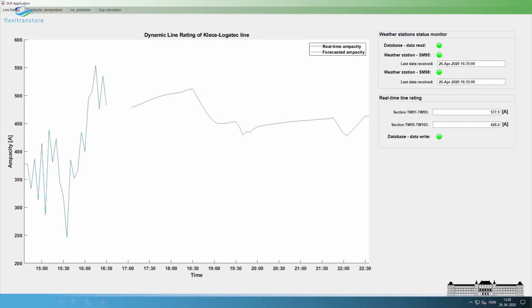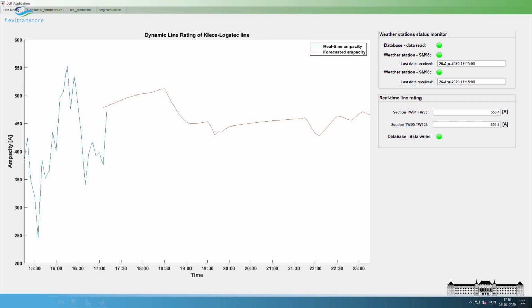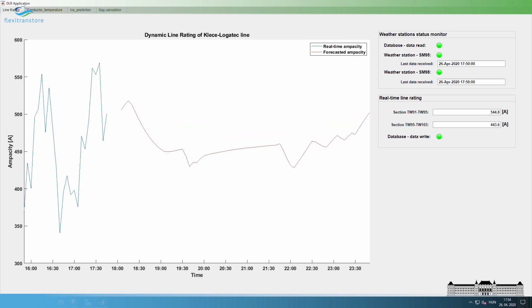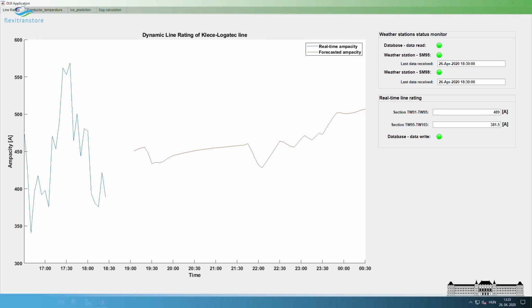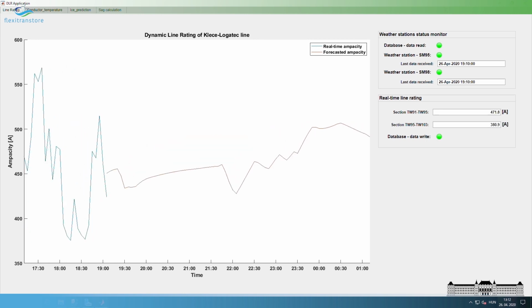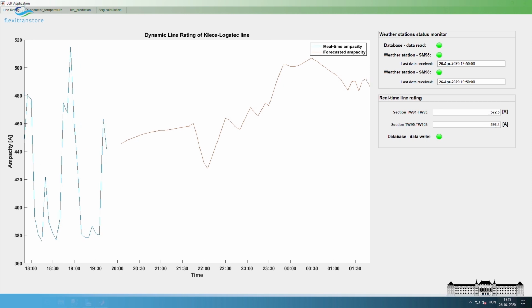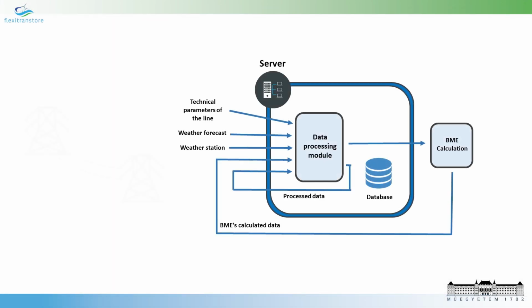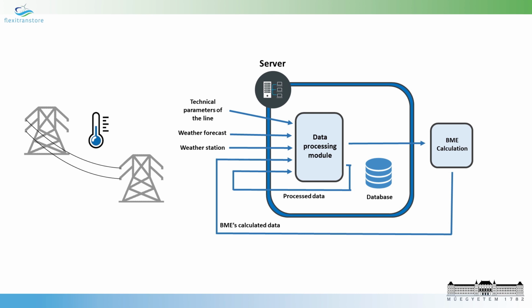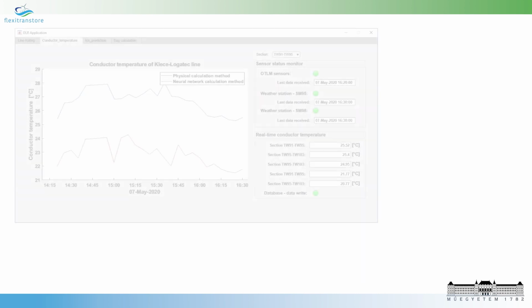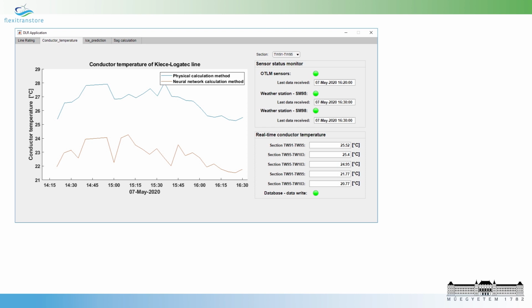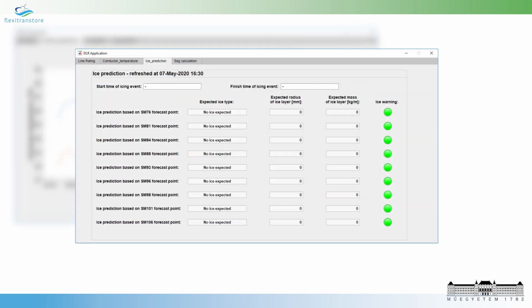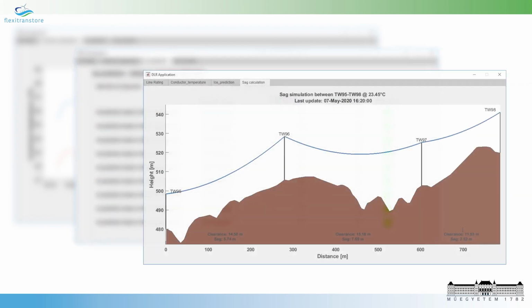The BME High Voltage Laboratory's DLR expert system was developed in order to monitor the actual thermal state of the conductors. For this purpose, the real-time and predetermined line rating are calculated with an extended physical model. This model also takes the cooling effect of precipitation into account. The conductor temperature is also tracked by a neural network-based model. The ice prediction subsystem is developed in order to forecast possible icing events on power lines. For safe and high thermal utilization of the conductors, the sag clearance is also tracked by the grid management system.